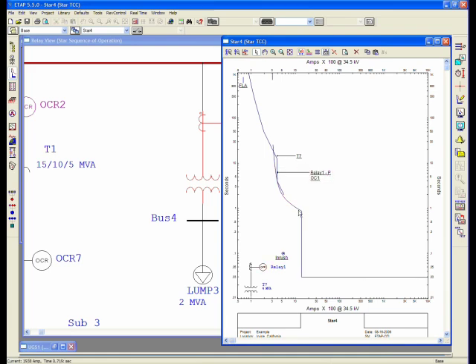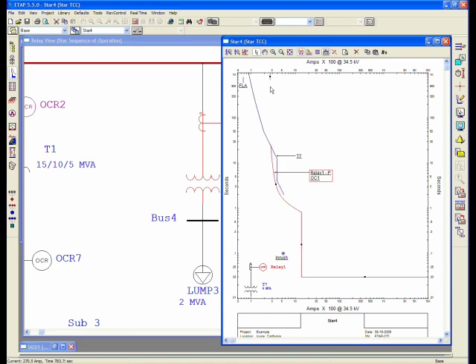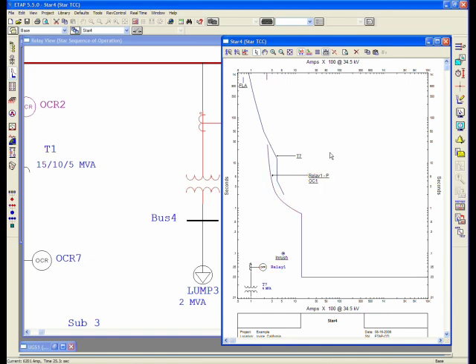Notice here, what I have is the transformer and the relay curve, and they're crossing each other. Obviously, I have a potential problem here because I got the knee point connected to here. So what I can do is change my relay pickup and bring it up to the point such as here.